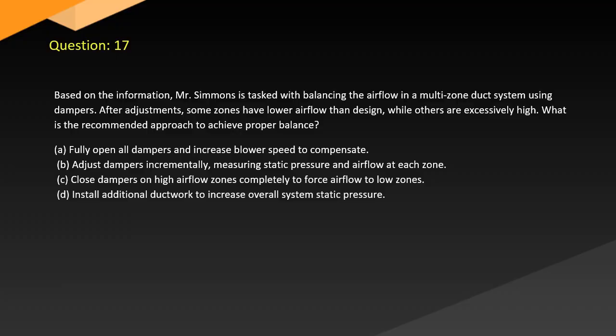Question 17. Based on the information, Mr. Simmons is tasked with balancing the airflow in a multi-zone duct system using dampers. After adjustments, some zones have lower airflow than designed, while others are excessively high. What is the recommended approach to achieve proper balance? A. Fully open all dampers and increase blower speed to compensate. B. Adjust dampers incrementally, measuring static pressure and airflow at each zone. C. Close dampers on high airflow zones completely to force airflow to low zones. D. Install additional ductwork to increase overall system static pressure.